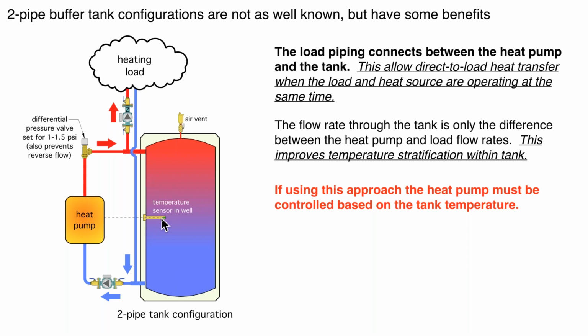So there are different control algorithms, I'll call them, but because of how this tank is piped this way, it's important that we control the heat pump based on that tank temperature. The other detail I want to stress is over here. One of the things that can happen, and we've seen this happen, is we'd like to think that when we send hot water up to the load and it cools down, it comes back down, and let's say the heat pump is off, okay? Heat pump's off. We'd like to think that the water has the intelligence to know when it gets to this T that it's supposed to go this way through the buffer tank and drive warm water back up through the load. It turns out water doesn't have much intelligence, all right? Or I could say maybe the water's outsmarting us if we don't put this certain detail in there.